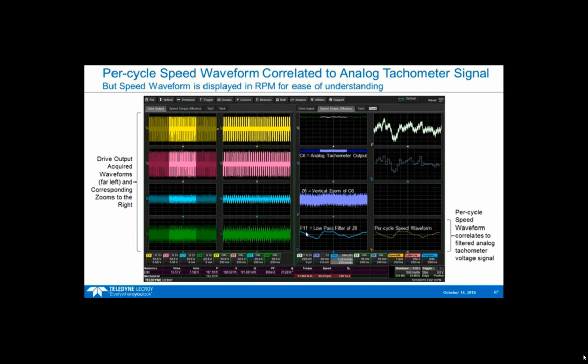Then I applied a math function. There's a built-in tool, if you choose to buy it, where you can put a low-pass filter on. This F11 trace is a low-pass filter of the Z6 signal, and I can filter that. I think it's down around 10 kilohertz or so. When I do that, I can see it closely tracks the per-cycle speed waveform. We have a built-in filter for the speed calculation, and it tracks very well. The difference is this value is displayed in RPM, and this value is displayed in voltage.